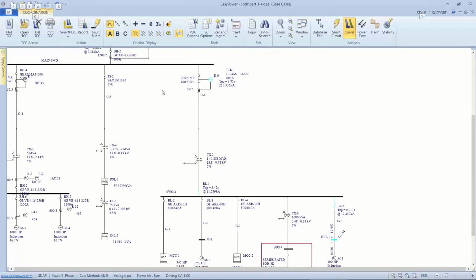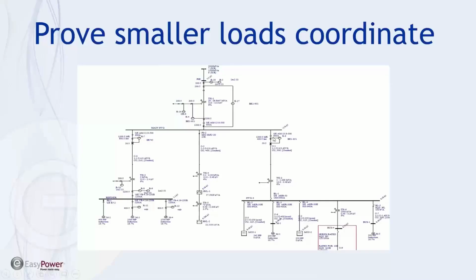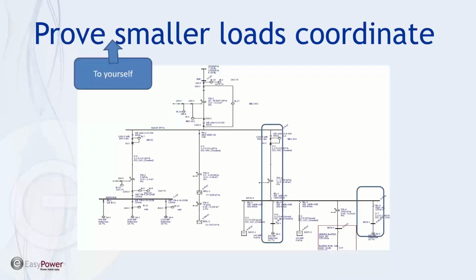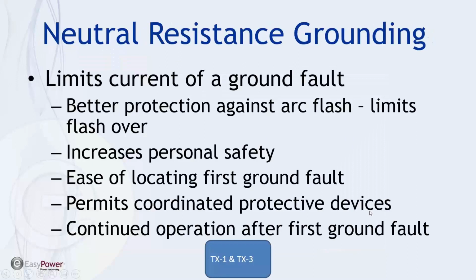So hopefully that was beneficial. And so again, what we essentially did was coordinate this leg with this leg, proving that smaller loads on that same bus will be coordinated. And now as long as this breaker or this relay is coordinated with this relay, I've got coordination for my whole system, at least on that side. And so I invite you to prove to yourself that this will be the case. If you've got the largest load coordinated on a downstream bus, then your smaller loads will be coordinated.